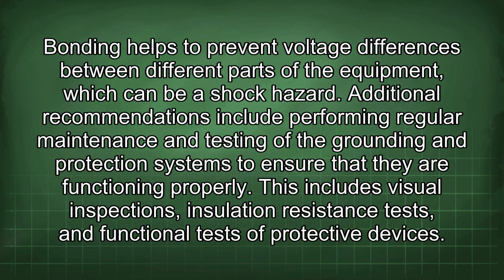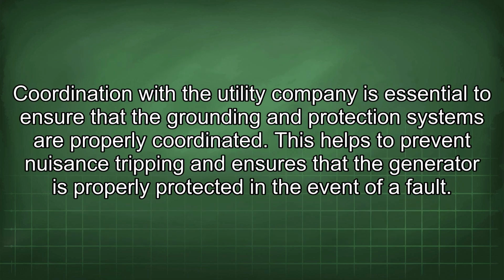Additional recommendations include performing regular maintenance and testing of the grounding and protection systems to ensure that they are functioning properly. This includes visual inspections, insulation resistance tests, and functional tests of protective devices. Coordination with the utility company is essential to ensure that the grounding and protection systems are properly coordinated. This helps to prevent nuisance tripping and ensures that the generator is properly protected in the event of a fault.